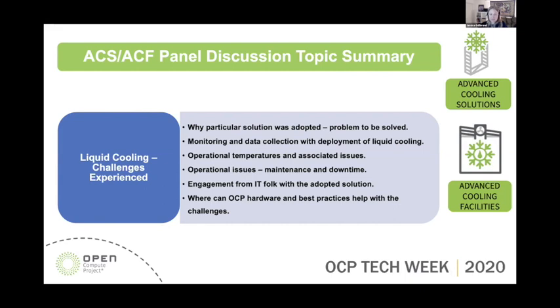So it's different requirements if you deal with cold plates versus immersion, they will likely want different types of IT equipment, and potentially changed-out materials to ensure compatibility with most liquids. But that's really the integration as a full system. I just want to stress that again as the highest importance for liquid cooling.